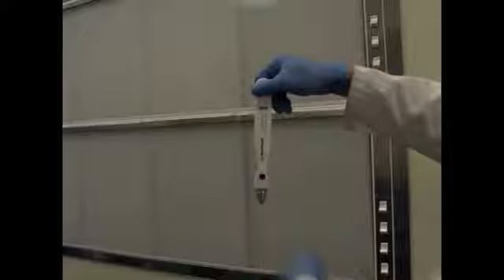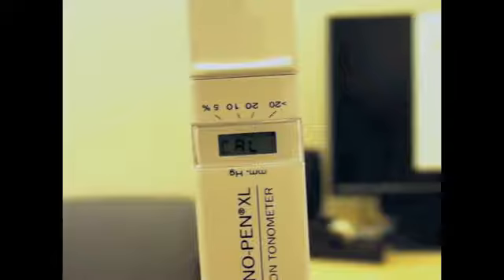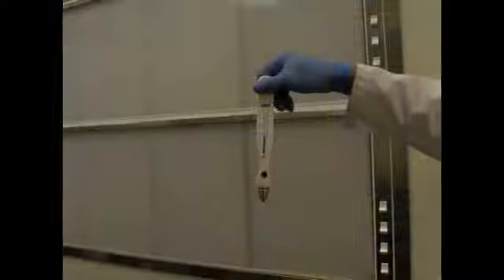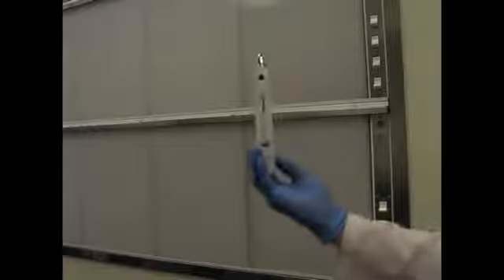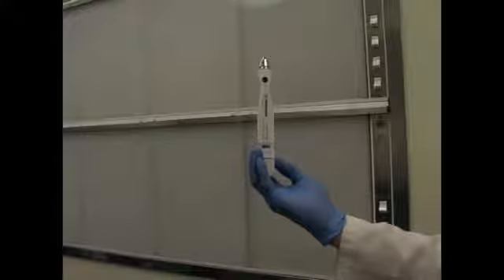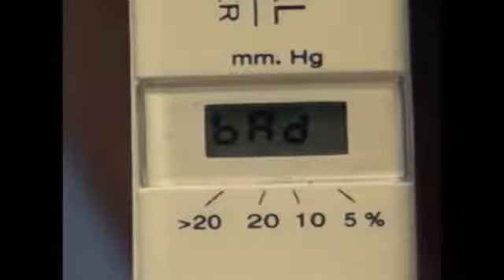Double-click the Calibrate button. After hearing 2 successive beeps, you should see the letters CAL. After a slight delay, you will hear another beep, accompanied by the text up. Point the tip of the pen upwards to complete the calibration. After a few seconds, you will hear another beep, accompanied with the words good or bad. If it was bad, repeat the calibration.